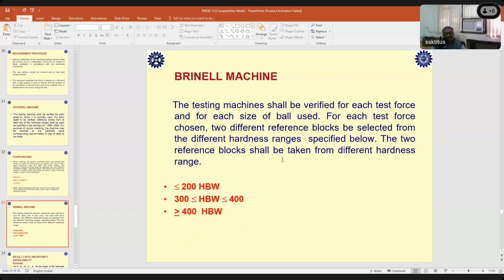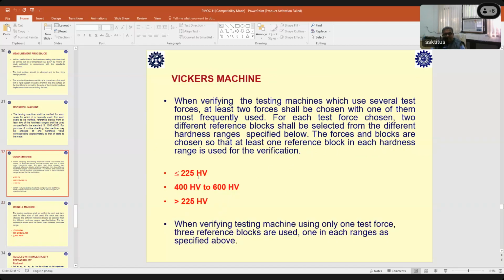The same thing is for the Brinell also. The testing machine shall be verified for each test force for each size of ball used. Here we are using different balls, 1 mm, 2.5 mm, 5 mm, 10 mm, and for all these balls you have to check whether the machine is properly functioning or not. And then this is the range. Even in Vickers, less than 225, because that's a smaller value, the error can be more in this range.